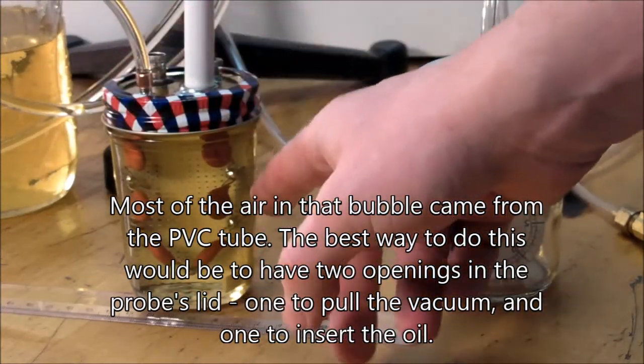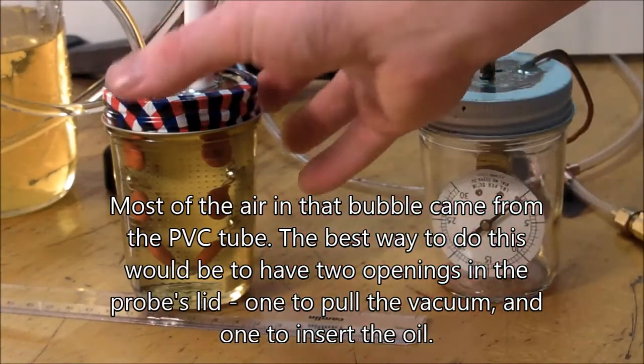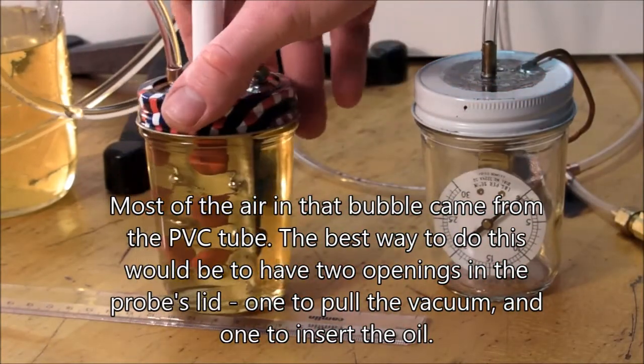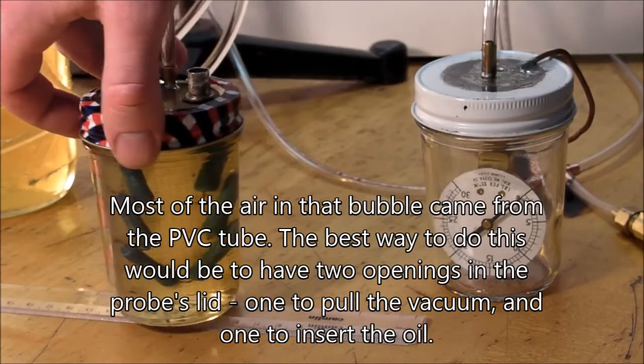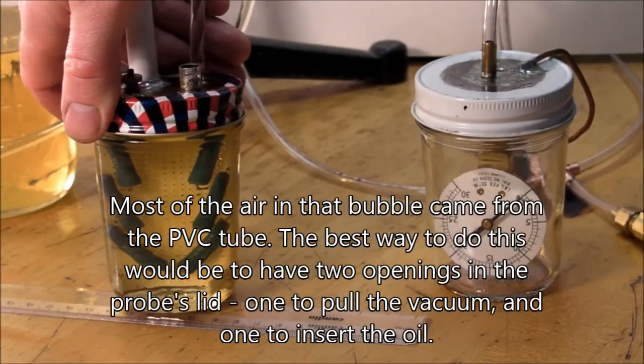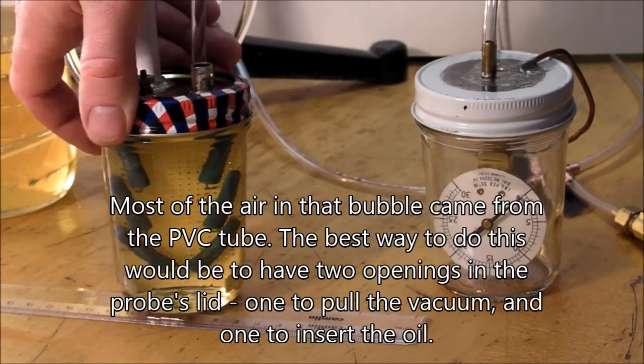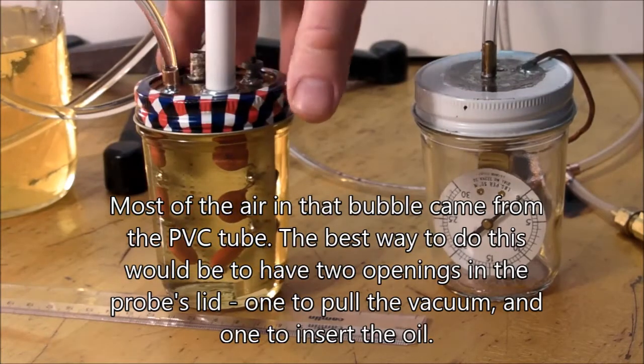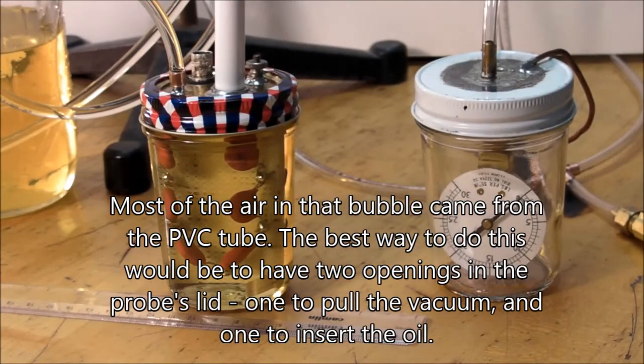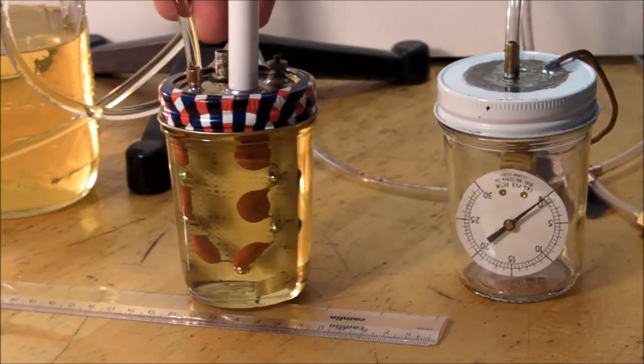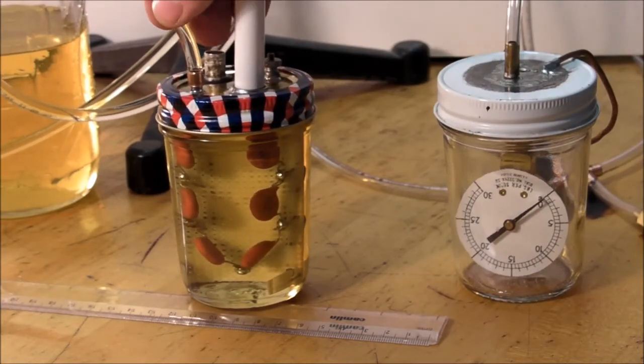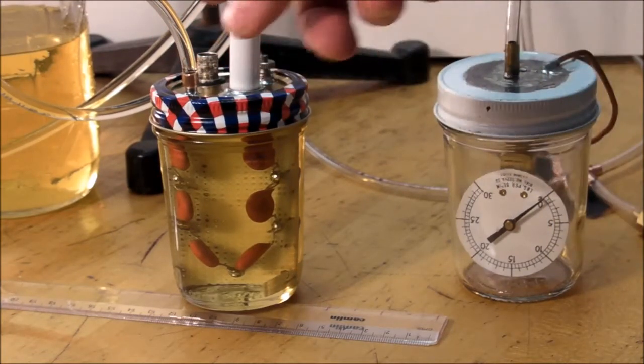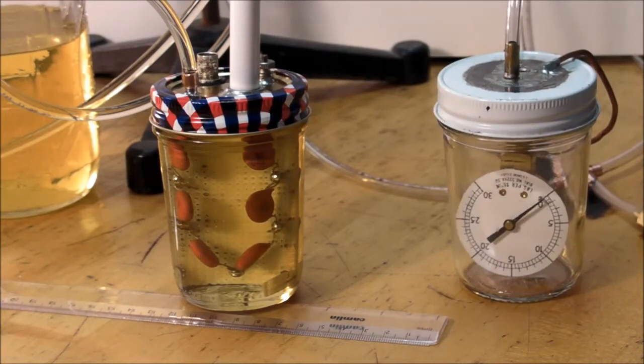Just as long as all the high voltage components on the bottom are fully immersed, I would say it looks pretty good. So I'm just going to pull this hose off and probably use a syringe to inject a little more oil in there to fill up that last little air bubble, and then put the cap on it, and I'm done.